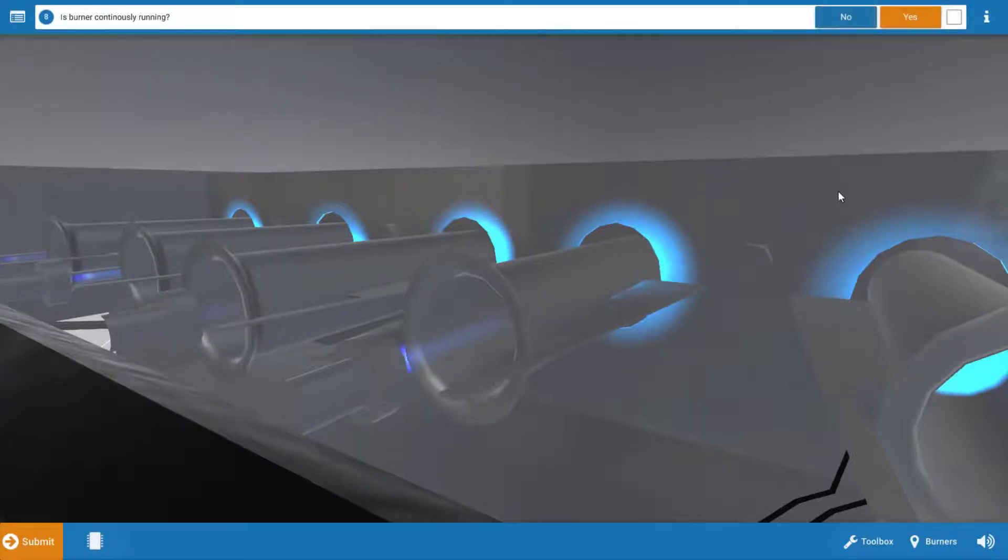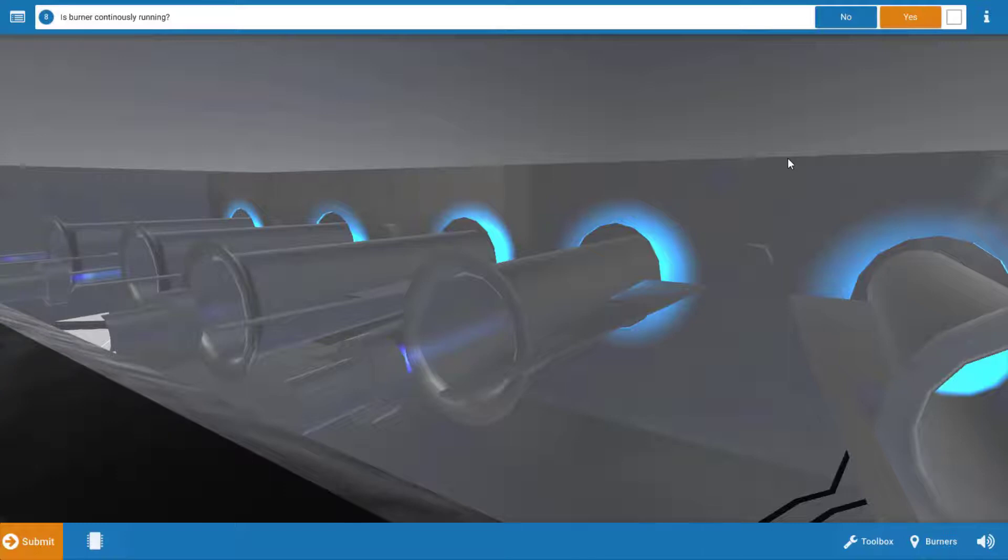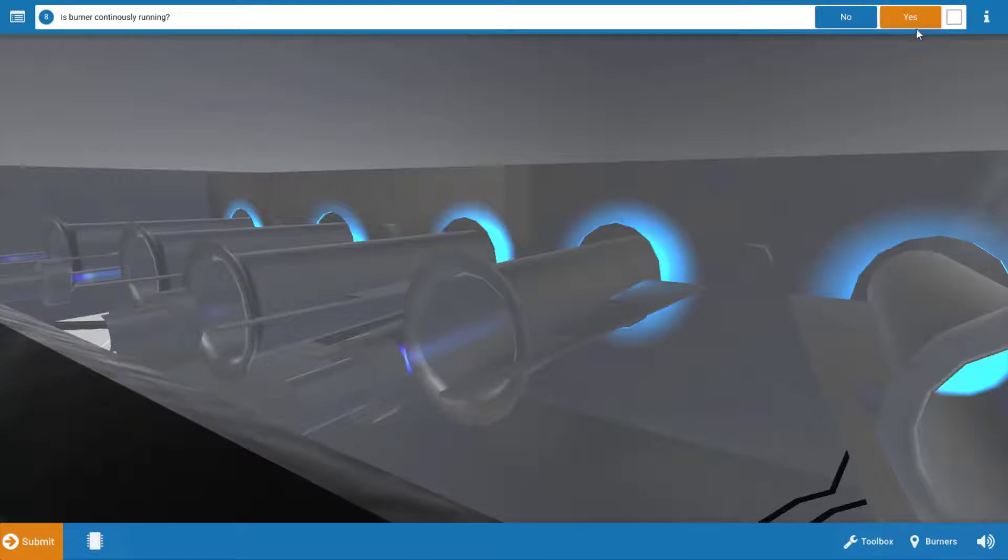Next, we want to verify if the burners continuously run. In other words, if we have an issue with a safety switch or a flame proving problem, the burners may light off, but then shortly thereafter they'll shut right off and they may cycle like this for a few times. But as we can see, the burners appear to stay on continuous, so we're going to click yes.